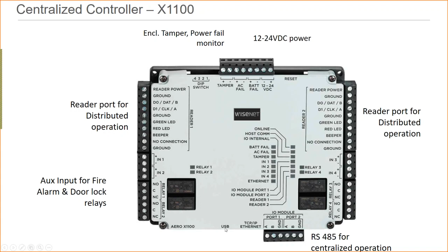Now we will be going through the examples, to apply what we just learned so it will be in our memory. The master controller, the main controller, can connect up to 32 subcontrollers. Agreed? In which method? The centralized method: central controller and then subcontrollers. Each subcontroller can connect up to two readers. The master controller has two RS485 ports, connecting 16 each. 16, 16, 32. 32 what? 32 subcontrollers. Each subcontroller has access to two readers, so 64 readers.